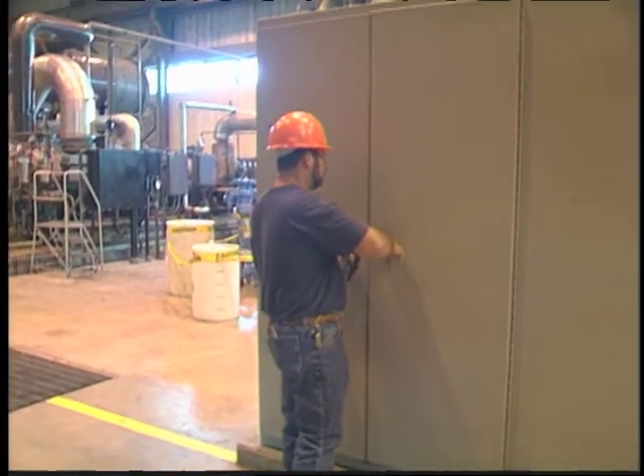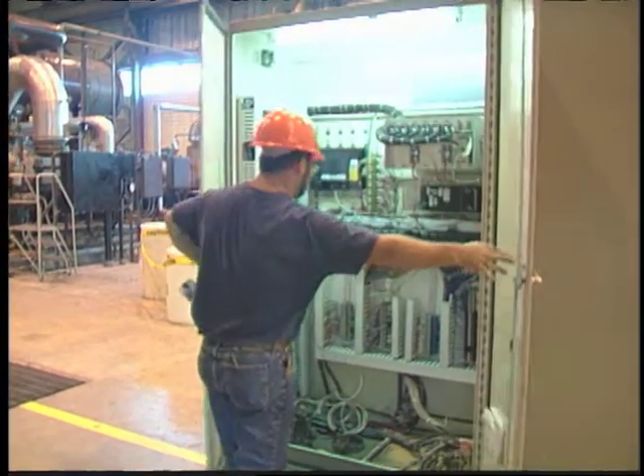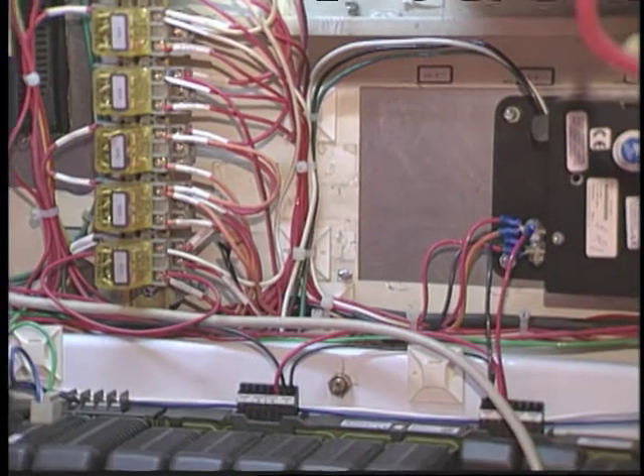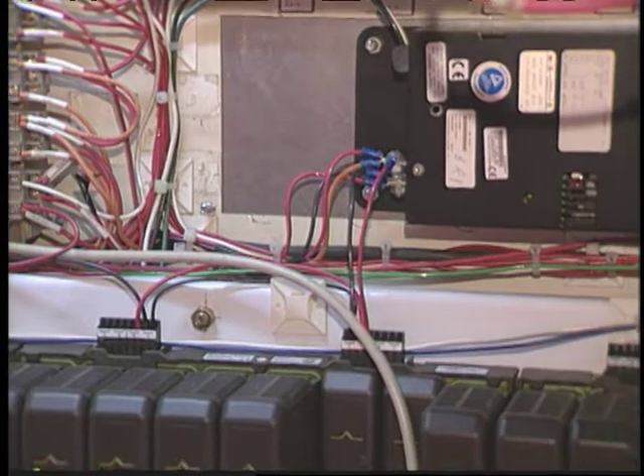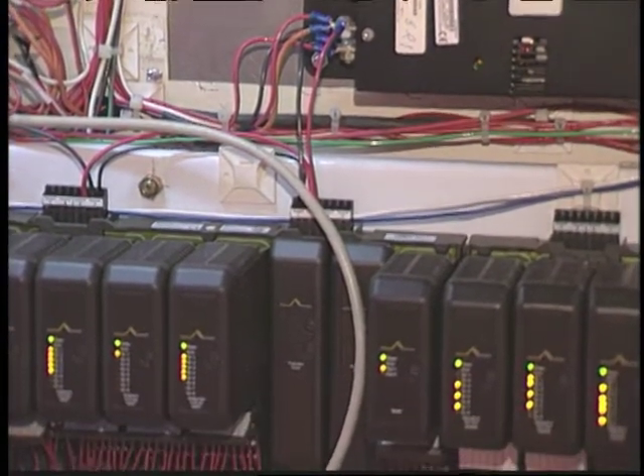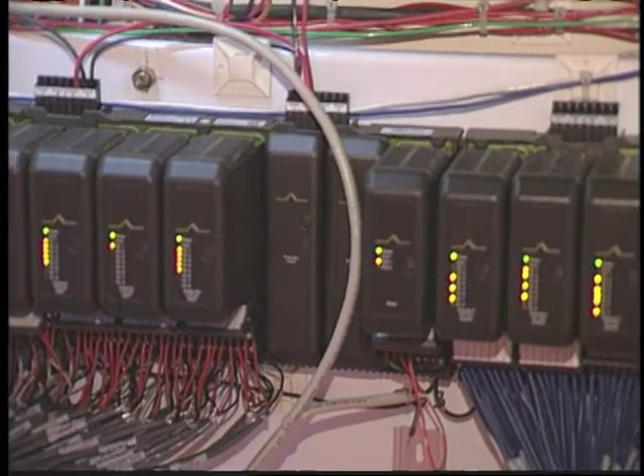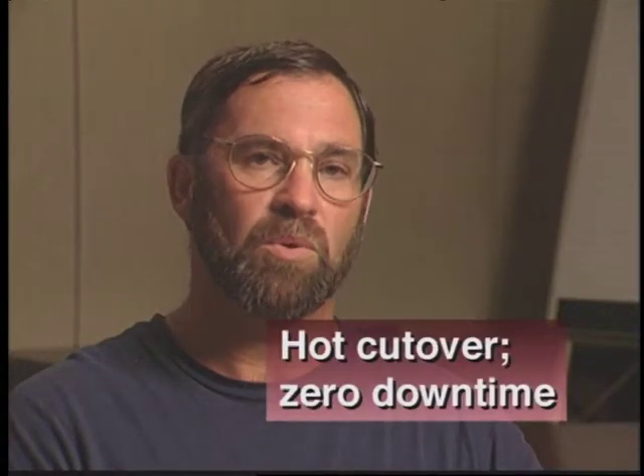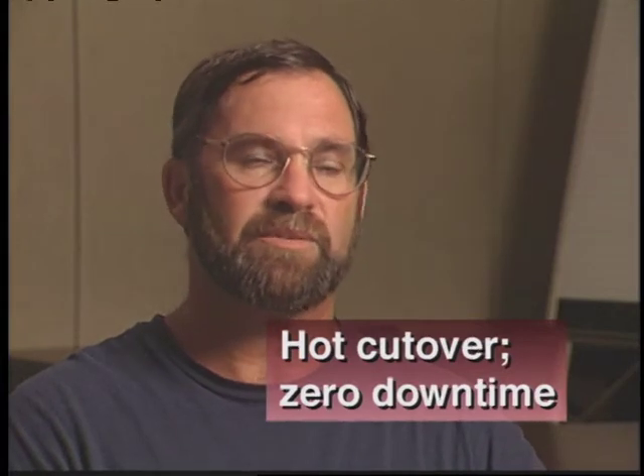So we had to temporarily hang the DeltaV while we changed over one cell at a time. The nightmare was having to keep the two systems running while online, because if you knock South Tower down, you knock the whole plant down. We had very few problems. In fact, management was very happy we were able to do this without knocking them down in any way, no loss of any pumps or fans, which is all critical equipment for the powerhouse.